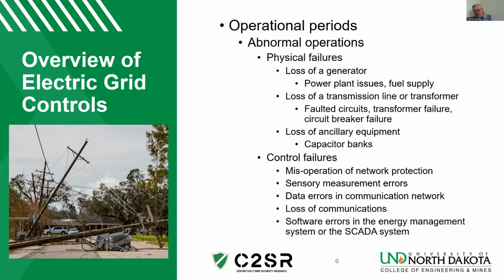That's a study amongst the relay committee members in various organizations to try to root out how to get rid of incorrect set points in network protection. Sensory measurement errors are always taking place. Instrumentation becomes uncalibrated over time. Equipment does age and fault out. And so sensory errors are always a common problem. And this gets elevated because that data is being collected across the system and being fed back to the energy management control system.